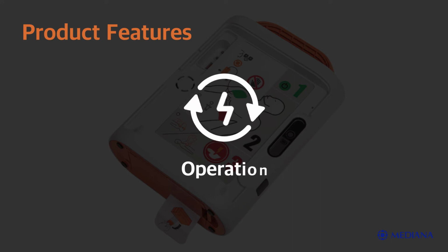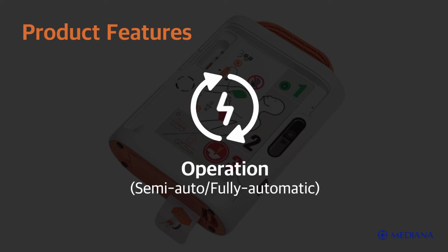Operation mode: fully automatic or semi-automatic operation is possible. When the A16 is set to fully automatic function, users don't need to press the shock button; the shock will be delivered automatically. When the device is semi-automatic, a flashing button indicates readiness for shock delivery, and users can push the button to deliver the shock.